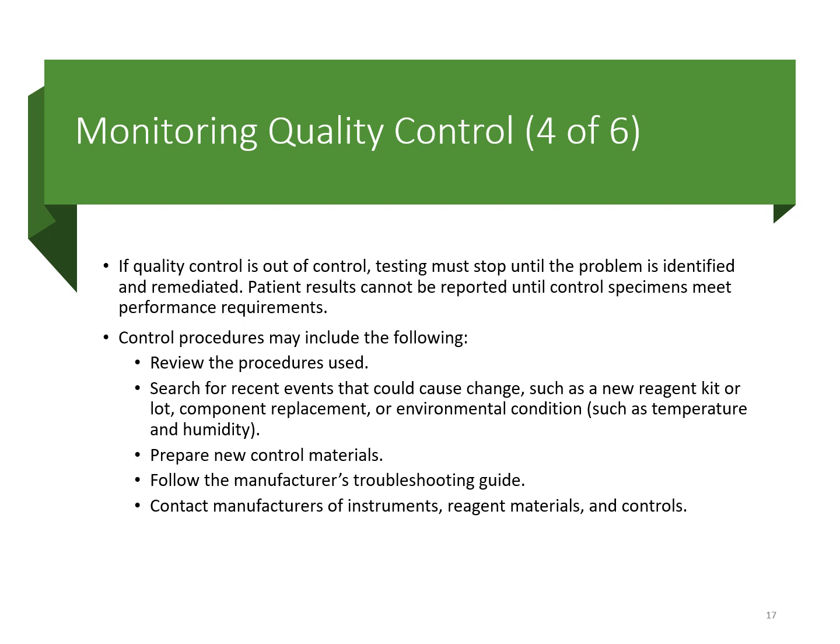And so part of that quality control procedure process is to actually evaluate and look at those results. So you'll run QC, get a report, look at it, and it's going to tell you if it's within acceptable limits. If it's not in acceptable limits, then you need to start looking at some things. So this may be doing some look backs, looking to see what made that error happen. Did you change the kit that you were using or those reagents? You've got a new lot number.